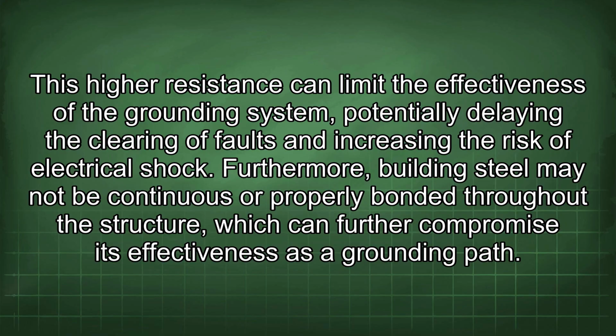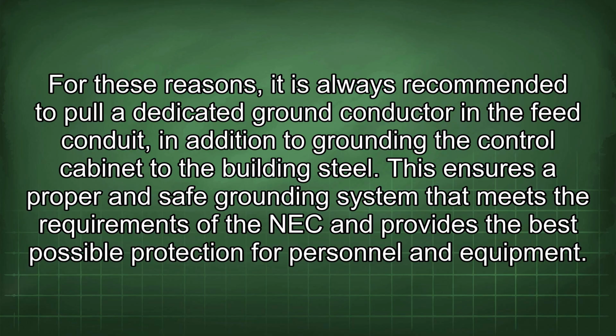Furthermore, building steel may not be continuous or properly bonded throughout the structure, which can further compromise its effectiveness as a grounding path. For these reasons, it is always recommended to pull a dedicated ground conductor in the feed conduit, in addition to grounding the control cabinet to the building steel. This ensures a proper and safe grounding system that meets the requirements of the NEC and provides the best possible protection for personnel and equipment.